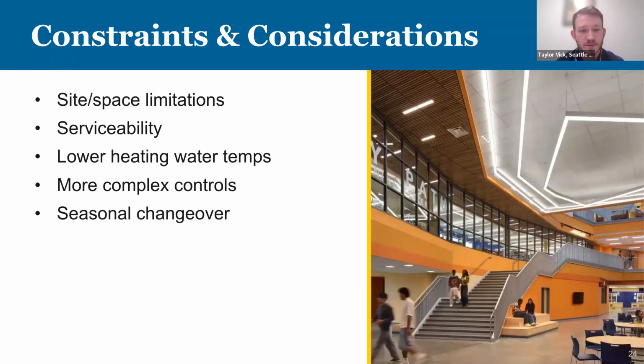Some considerations as well for the different types: heat pumps generate water at a lower temperature, so they're not going to be as effective in an older building where systems are designed for 160 or 180 degree hydronic hot water. You might not be able to retrofit the same type of equipment in those spaces, so consider that if you're looking to add heat pumps to an existing building.